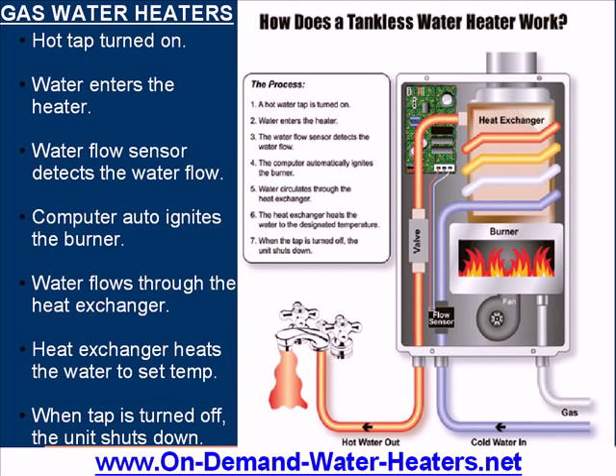You'll never run out. As soon as you turn your tap off, though, the flow sensor detects there's no more water flow through and automatically shuts off the burner. And then of course that's where your savings come in, because the burner's off. You don't require any more hot water.